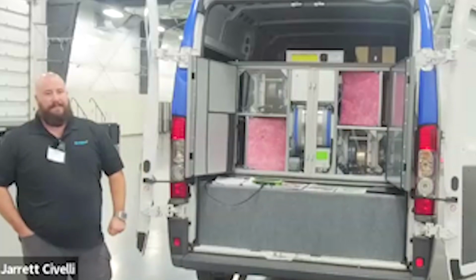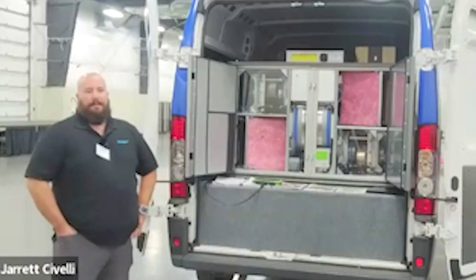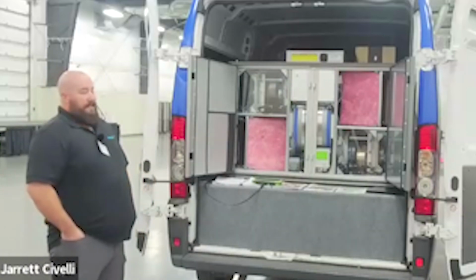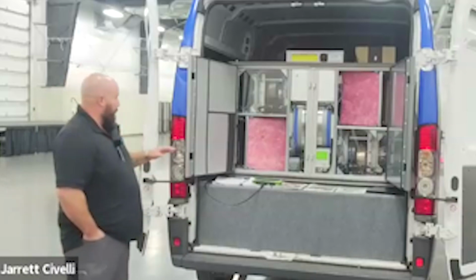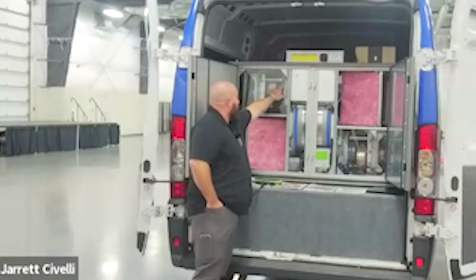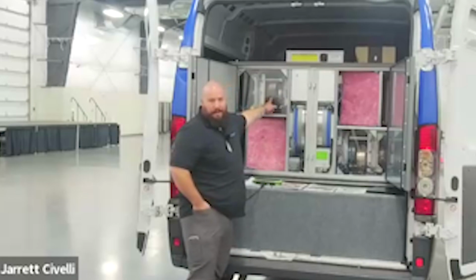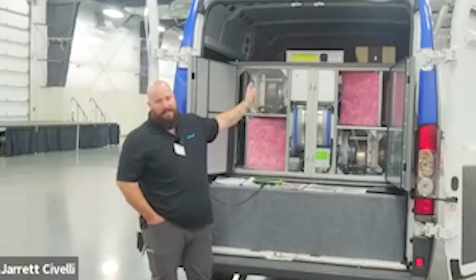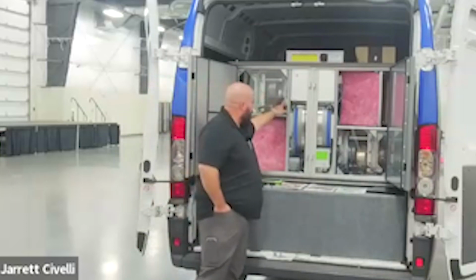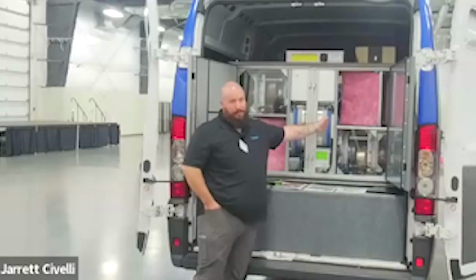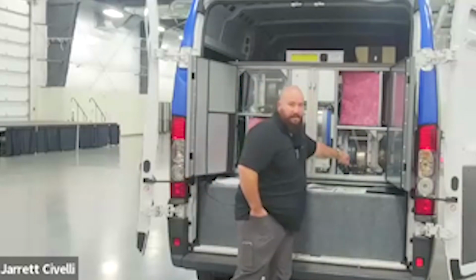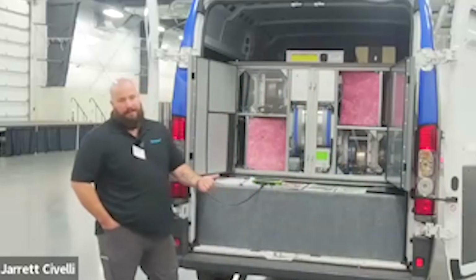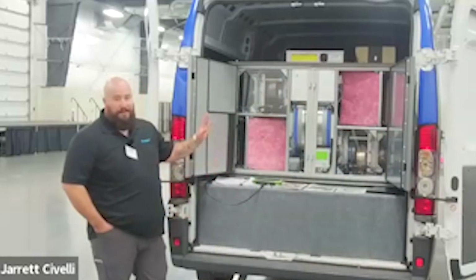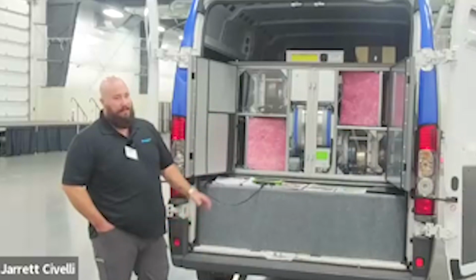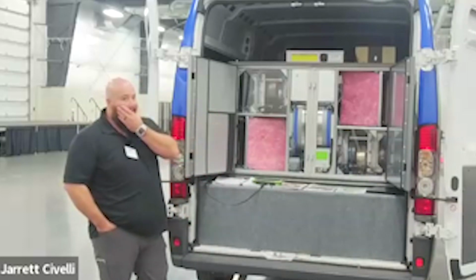I'm sure, does it have differential pressure, like checking that across the filters? And yeah, so the amount of sensors is pretty wild. There's a pressure transducer here with some tubing checking across the fan volute. That's checking the pressure across the fan and then calculating that into CFM. There's another pressure transducer here that's checking the pressure across the wheel. Same thing for this fan. So we have pressure across the fan plus CFM. The amount of information it'll give you is almost ridiculous. Temperature sensors on both sides.